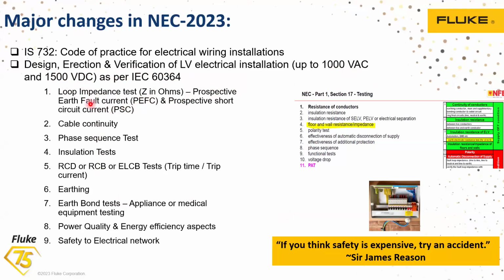Now under this, what are the recommended tests? Loop impedance test, that is fault current testing, is one of the major ones. When testing loop impedance, we have to ensure the device is capturing the earth fault current as well as the prospective short circuit current. Then the cable continuity. The cable continuity is not the normal continuity which we do with multimeters, because there is a recommendation that the device has to inject some amount of current to measure the cable continuity.